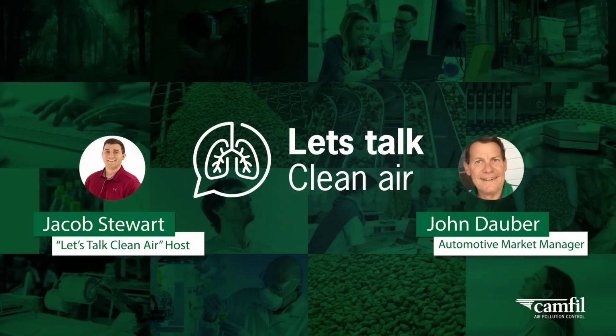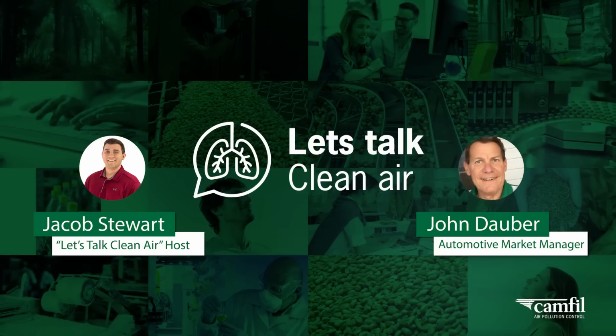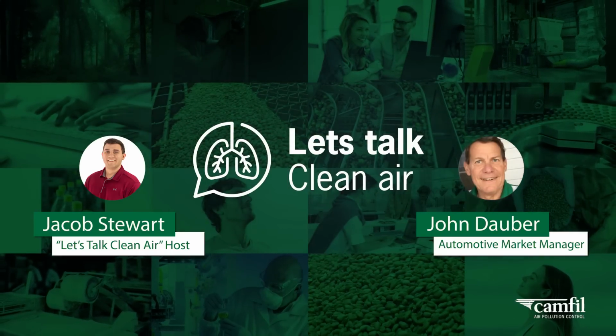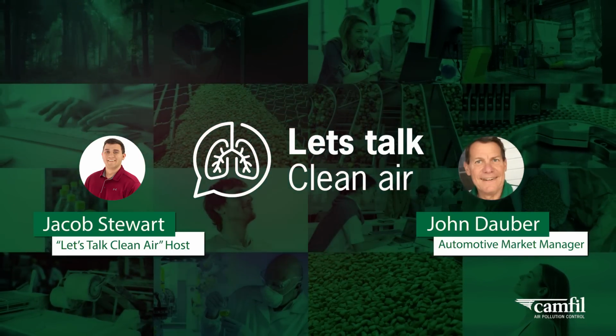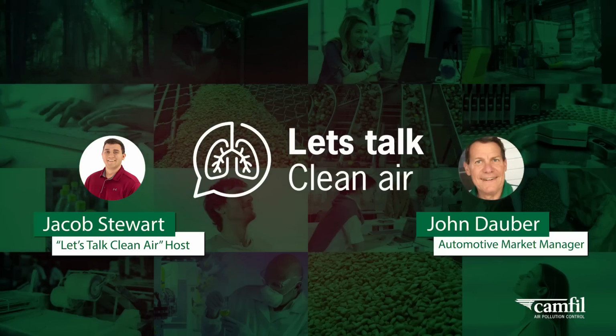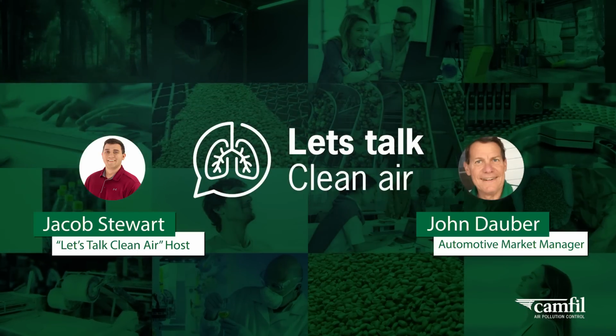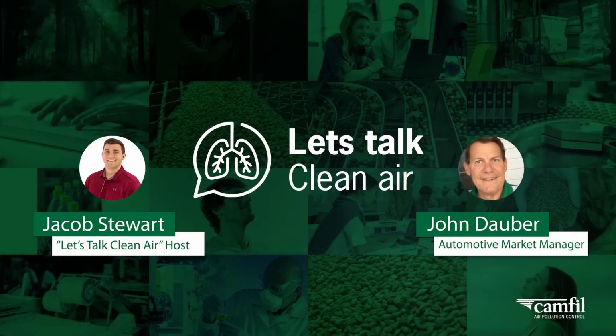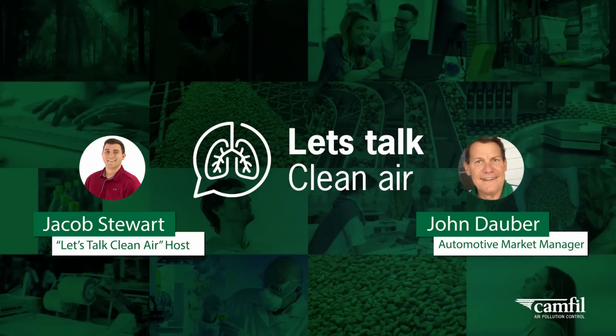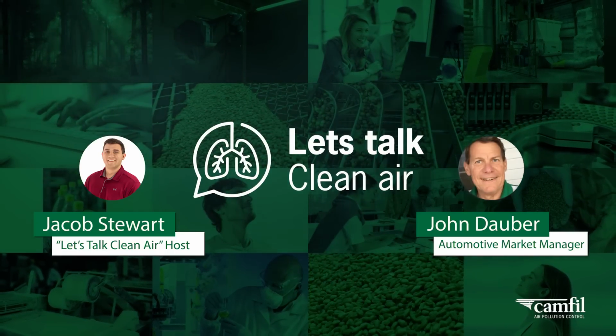media is really important. For instance, if we're dealing with a combustible dust, we use carbon impregnated cartridges that take the static electricity out of the cartridge itself, which could create a spark and cause issues in igniting combustible dust.